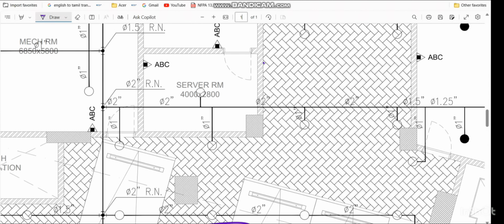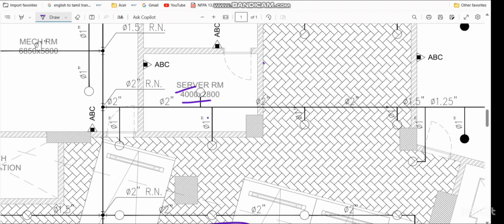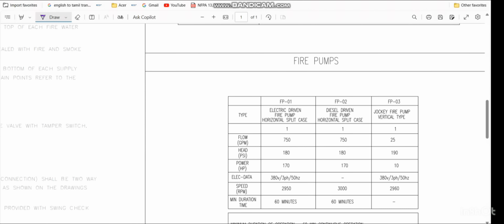Similarly, you can see this server room, 4 into 2.8. So 4 into 2.8, it will be 11.2. So again, we have to provide the clean agent system. Sprinkler is not allowed in the server room, it will damage.